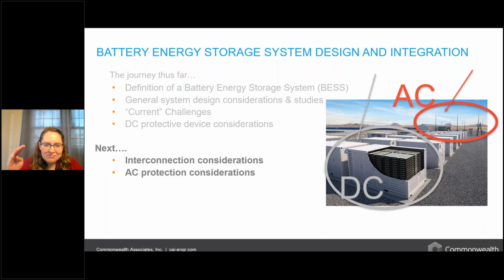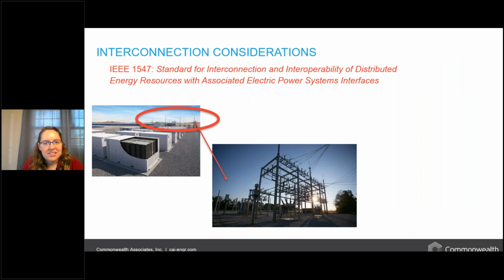Look out there. We see in our picture that batteries can actually connect to the grid, either at the transmission level or the distribution level. So specifically, let's talk about what happens when we connect community-based generation resources, like batteries, to the power grid on the distribution side. So for battery energy storage system design and integration, what are some interconnection design considerations?